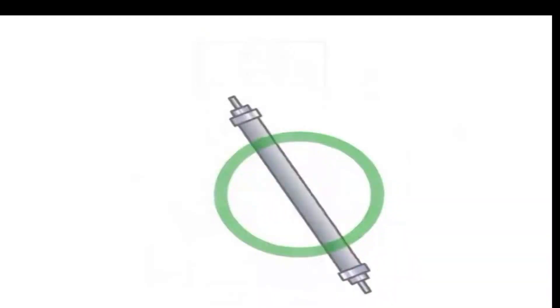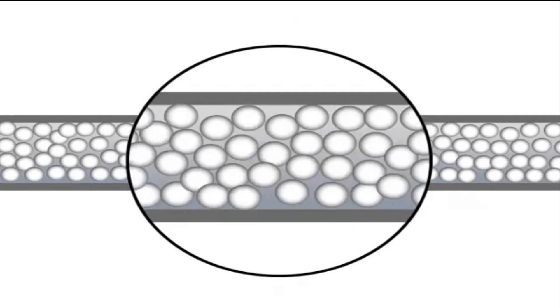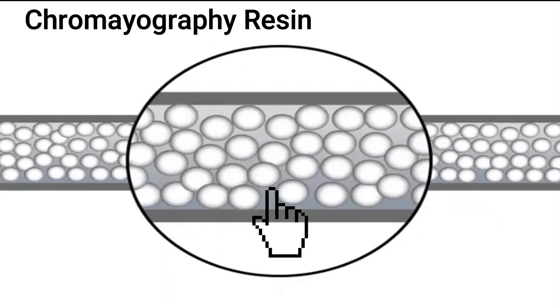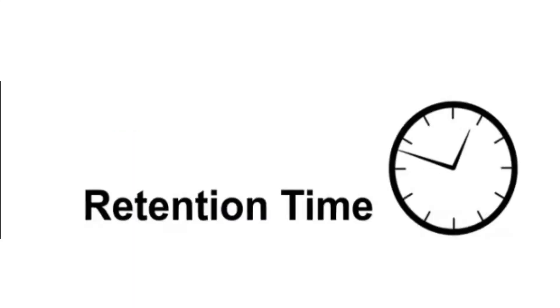The HPLC column is a key component to the system. It is composed of a metal or plastic cylinder packed with micro-scale beads of stationary phase, or chromatography resin. The sample flows through the packed particle bed at a constant flow rate and interacts with the stationary phase differently, therefore traveling down the length of the column to the detector at a different rate. The time required for a component to exit the column, or elute, is called the retention time.